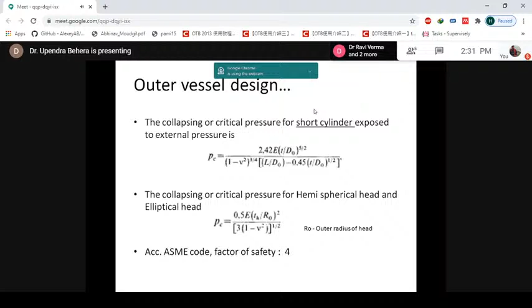This suspension system supports and suspends the inner vessel within the outer vessel, and should take the load of the vessel along with the weight of the content, that is the liquid inside when it is in full capacity, plus the dynamic load. If the suspension system is not good, it will nullify the effect of the insulation connecting the inner vessel to the outer one, so the insulation's effectiveness is lost, a lot of heat transfer occurs, and you cannot store the cryogens properly.